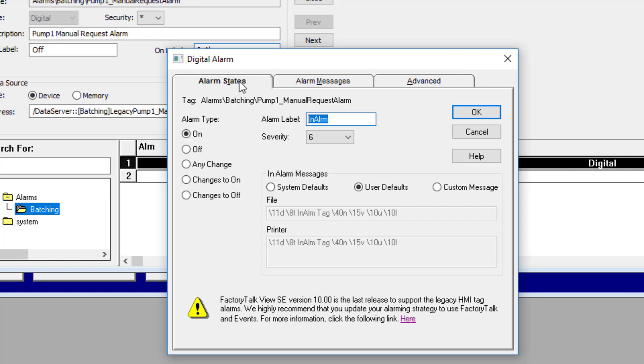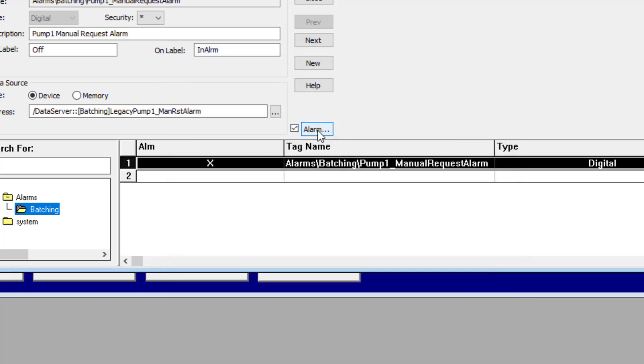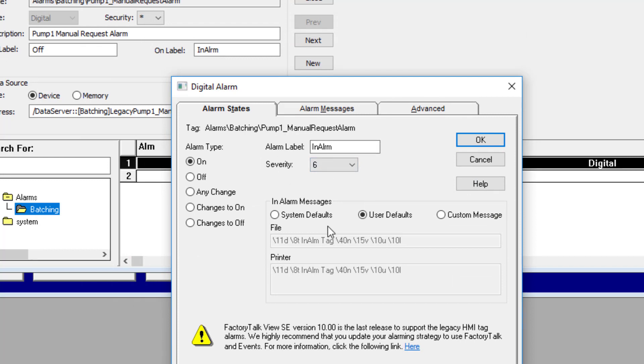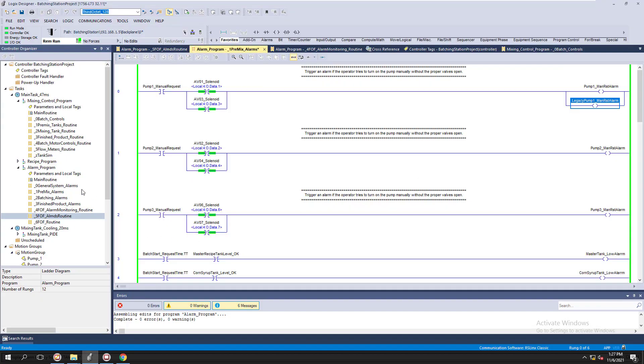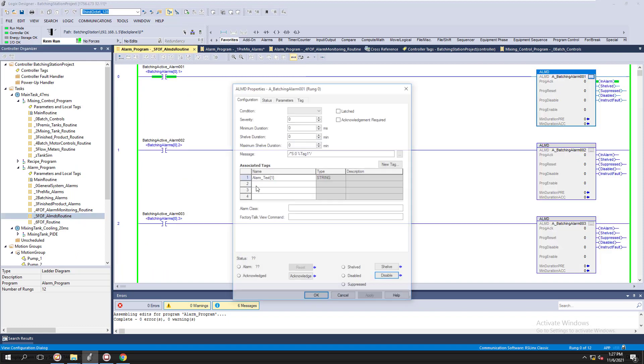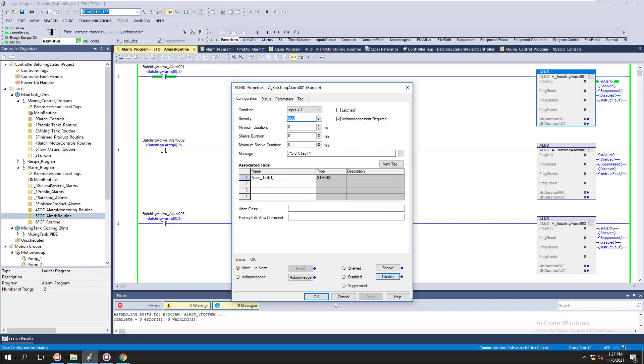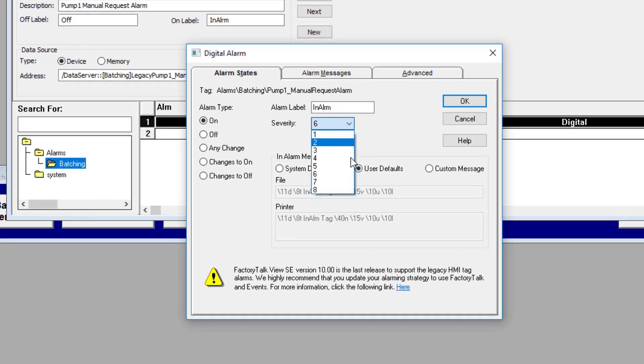So you create an alarm. You check the checkbox and then click the button — this creates and makes it an alarm. You want to say what type of alarm it is. This is a digital — just a transition from zero to one. So the type is triggered when it's On, or you can set it for Off, whatever your case requires. You can change your severity level here. I have this current alarm set at high severity to match my ALMD, which is also set at high severity.